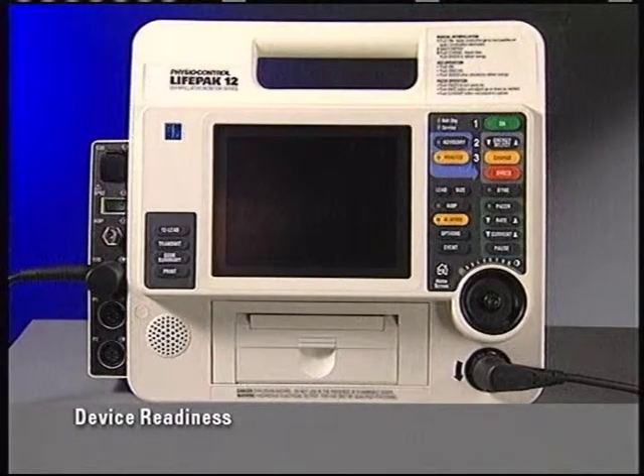Periodic inspection and testing of the LifePak 12 defibrillator monitor helps to ensure that the defibrillator is ready for use at all times. An operator's checklist is provided in the operating instruction manual. It is a suggested checklist to inspect and test the defibrillator. It may be photocopied for your use. This checklist is not a replacement for preventive maintenance tests, which should be performed regularly by qualified service personnel.